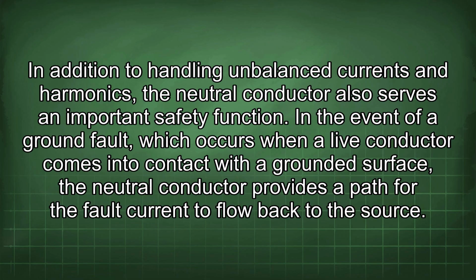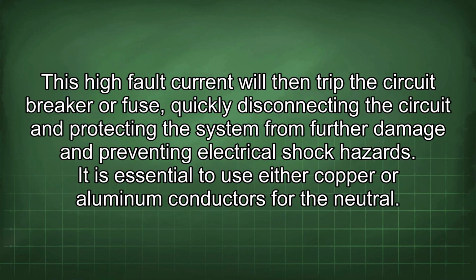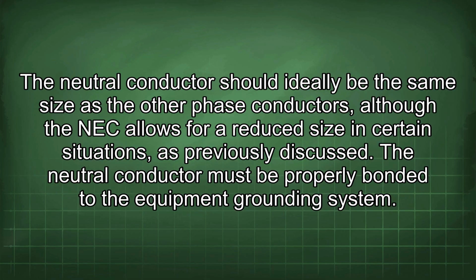In addition to handling unbalanced currents and harmonics, the neutral conductor also serves an important safety function. In the event of a ground fault, which occurs when a live conductor comes into contact with a grounded surface, the neutral conductor provides a path for the fault current to flow back to the source. This high fault current will then trip the circuit breaker or fuse, quickly disconnecting the circuit and protecting the system from further damage and preventing electrical shock hazards. It is essential to use either copper or aluminum conductors for the neutral. The neutral conductor should ideally be the same size as the other phase conductors, although the NEC allows for a reduced size in certain situations, as previously discussed.